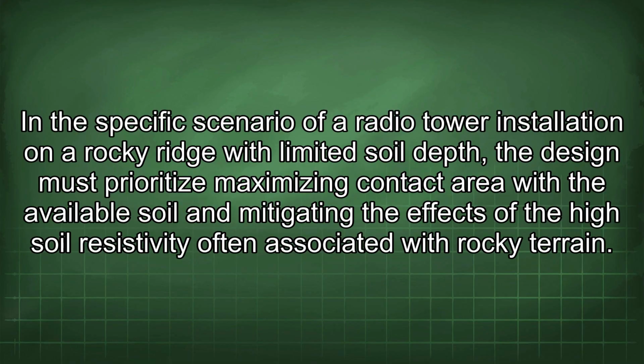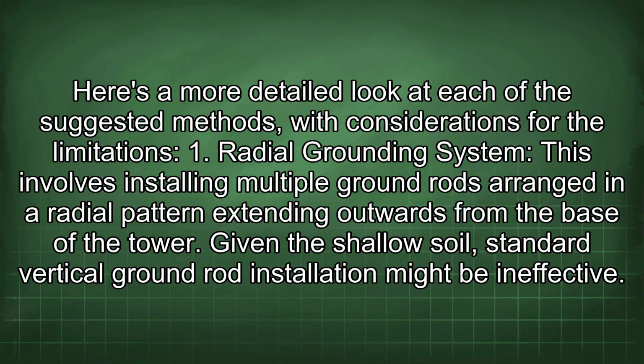In a specific scenario of a radio tower installation on a rocky ridge with limited soil depth, the design must prioritize maximizing contact area with the available soil and mitigating the effects of the high soil resistivity often associated with rocky terrain. Here's a more detailed look at each of the suggested methods, with considerations for the limitations. 1. Radial grounding system.